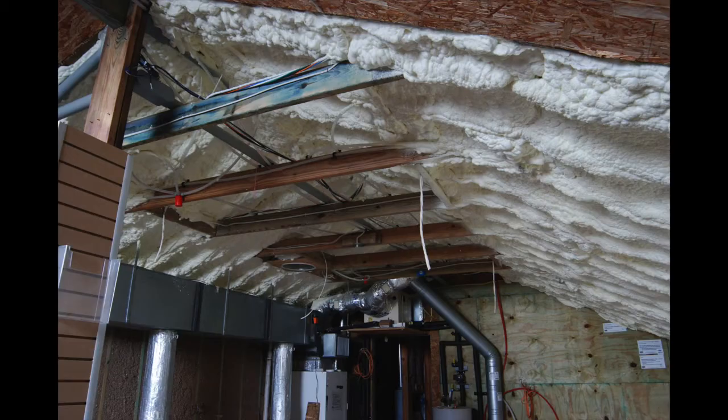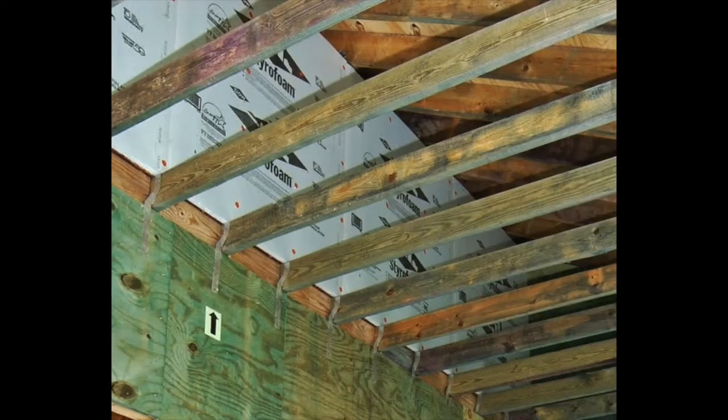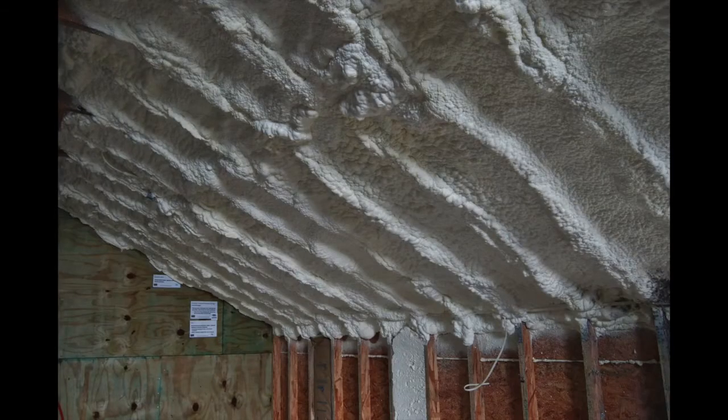The attic in this section of LaHouse is a specially detailed unvented attic with R30 open cell spray foam under the roof decking with a fire retardant coating. Plus, knee walls are insulated to R19 like the outside walls, and there is no insulation on the attic floor. Why do this? It does cost more than insulating the attic floor, but can offer several benefits.